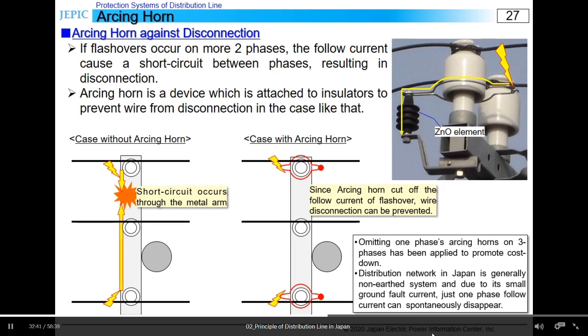By the way, omitting the arcing horn on one phase of the three phases has been applied to cut down the cost because it is said that the failure suppression effect is almost the same. Japanese distribution lines are basically known as the non-effectively grounded system, and its ground fault current is small, so the follow current of a flashover of just one phase without an arcing horn disappears by itself spontaneously.